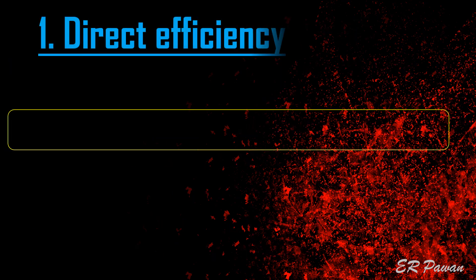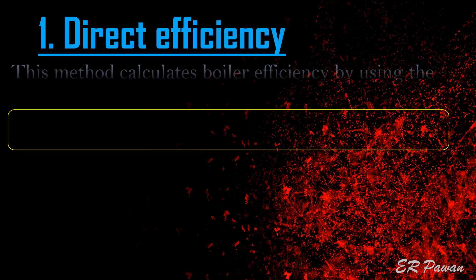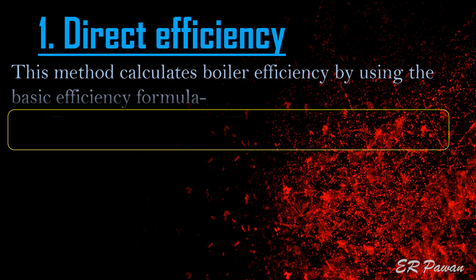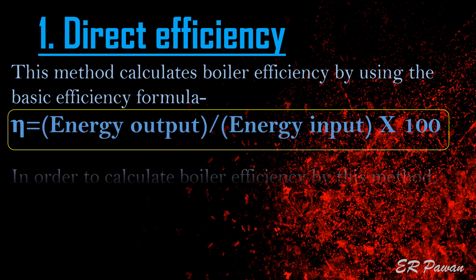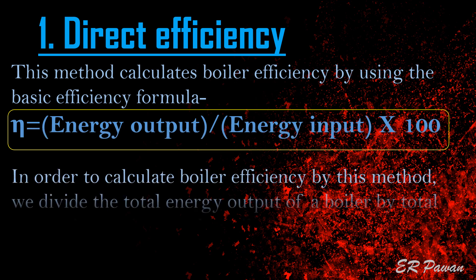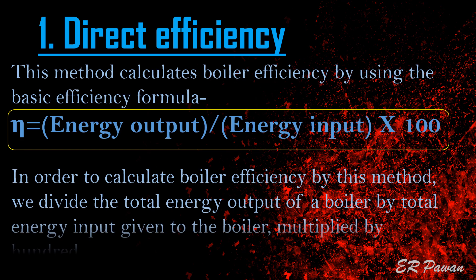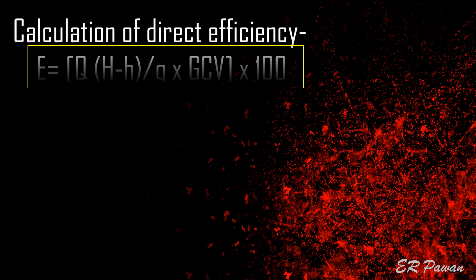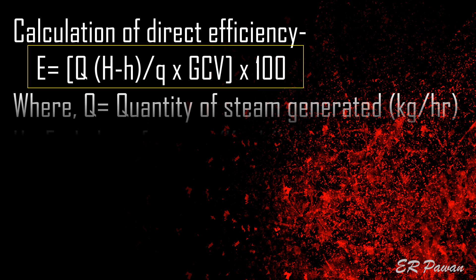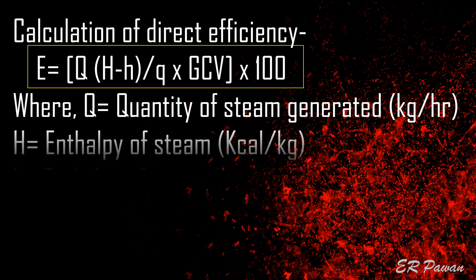Direct efficiency: this method calculates boiler efficiency by using the basic efficiency formula. In order to calculate boiler efficiency by this method, we divide the total energy output of a boiler by total energy input given to the boiler, multiplied by 100. The formula is: E = Q × (H − h) / (q × GCV) × 100.